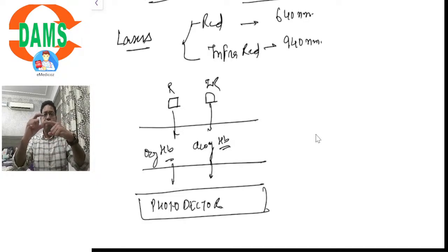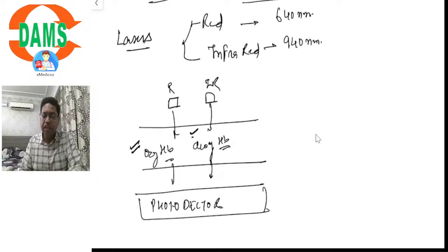Okay. If you remember, pulse oximeter is a device that clips onto the finger. From one end, the light is being fired, and from the other end, it is read by the photodetector. How much of the red or the infrared light would come out from the opposite side depends upon the amount of oxy and deoxyhemoglobin. So basically, it gives an idea about the blood oxygen saturation level.